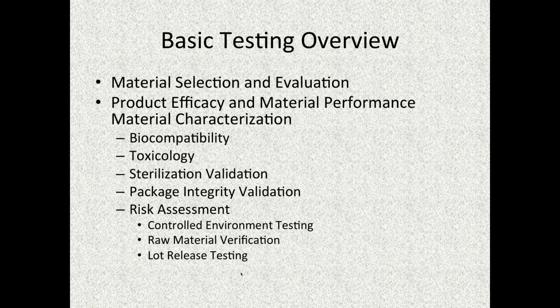The basic testing overview, taking a look at the material characterization, toxicology, biocompatibility, sterilization, validation. I introduced these here because these are in addition to the biocompatibility and toxicology studies. If you're going to sterilize your product in a package, your package integrity needs to be tested, as well as your sterilization method. There's only a few of them.